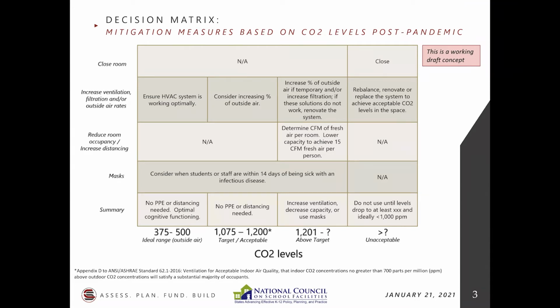Oh, sure. Carbon dioxide walkthrough measurements are truly a snapshot. And, I mean, seriously, the only way to get meaningful carbon dioxide data is to take real-time data. So you're logging data over a period of time, and you're looking at that as a data set as a whole. That's the gold standard.